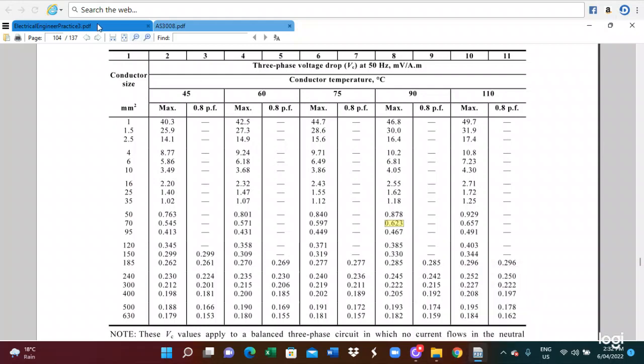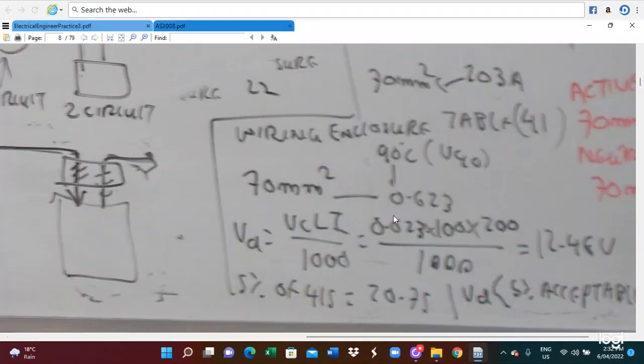So this VC value we substitute here, and the length is 100 meter. Current is 200, divided by 1000. You get 12.4 volt. The 5% of the three-phase voltage at 415 volt is more than 12.4 volt. So in this case it is less than 5%, so this is acceptable.